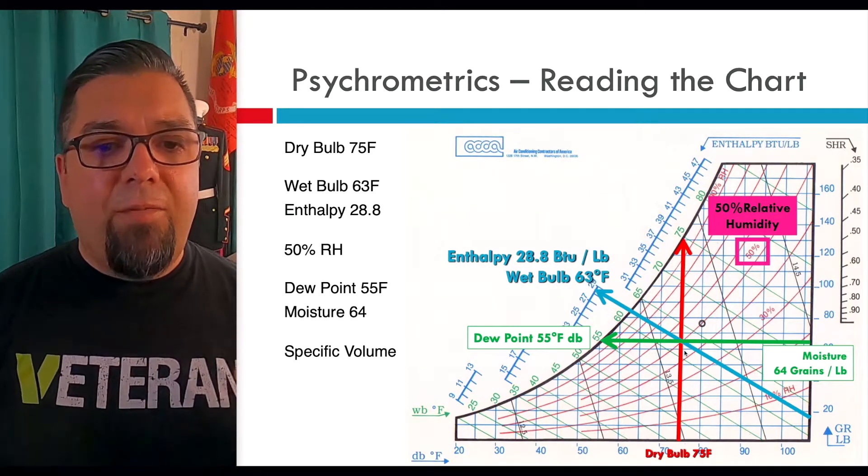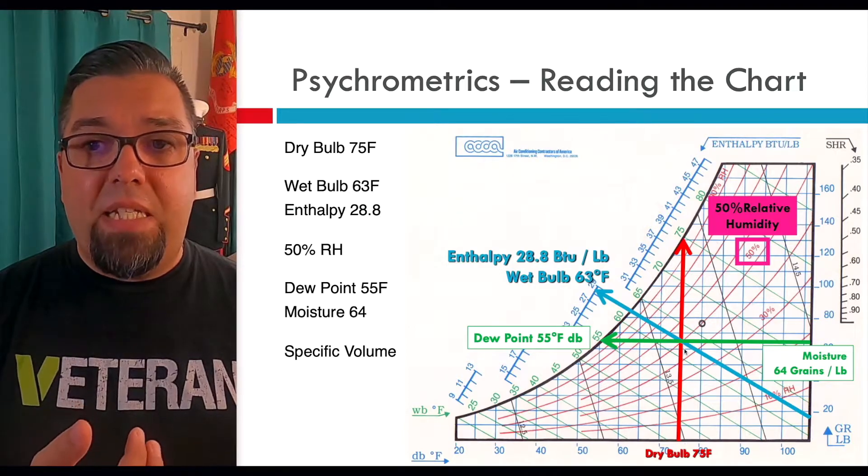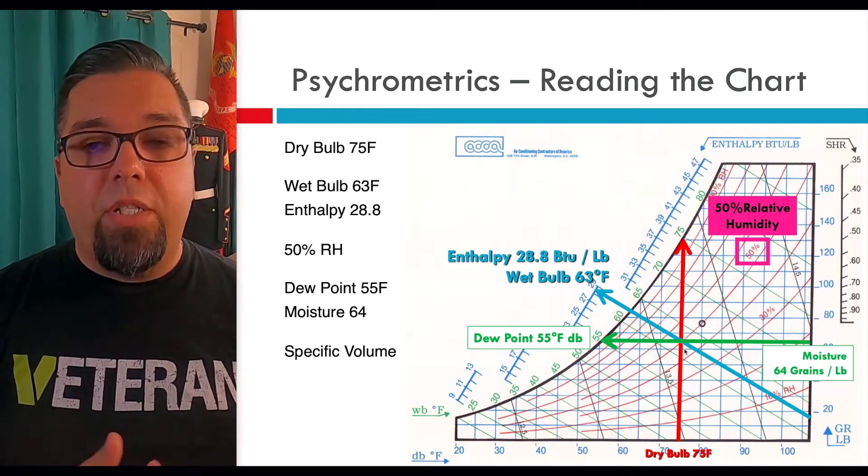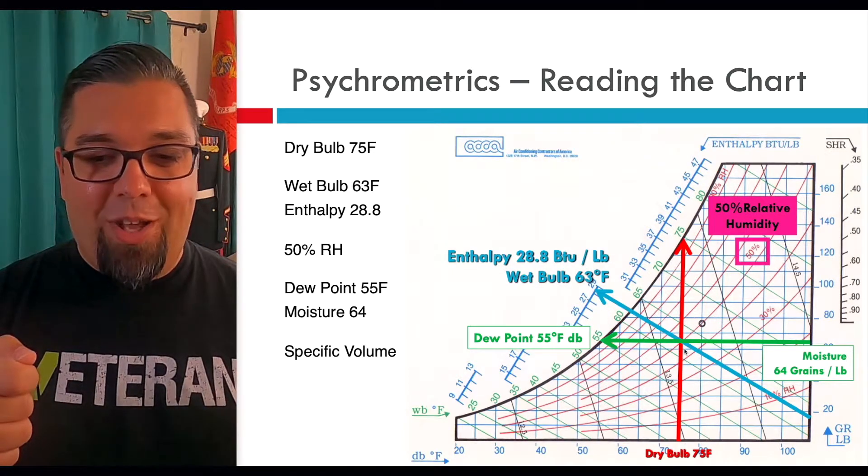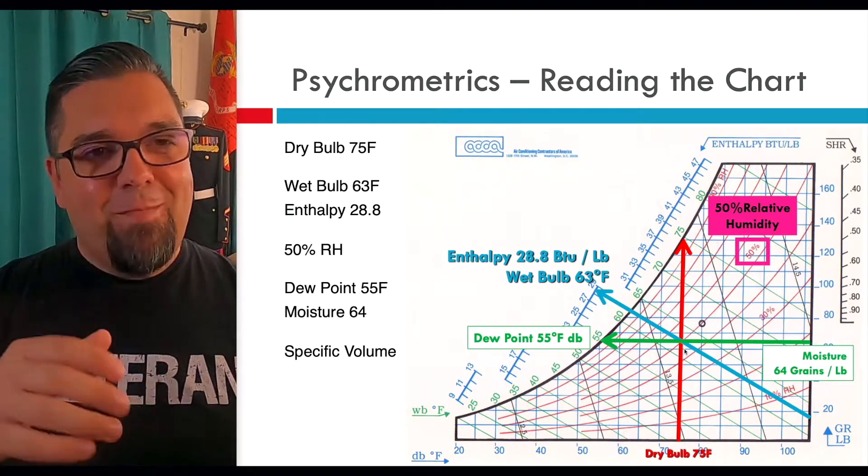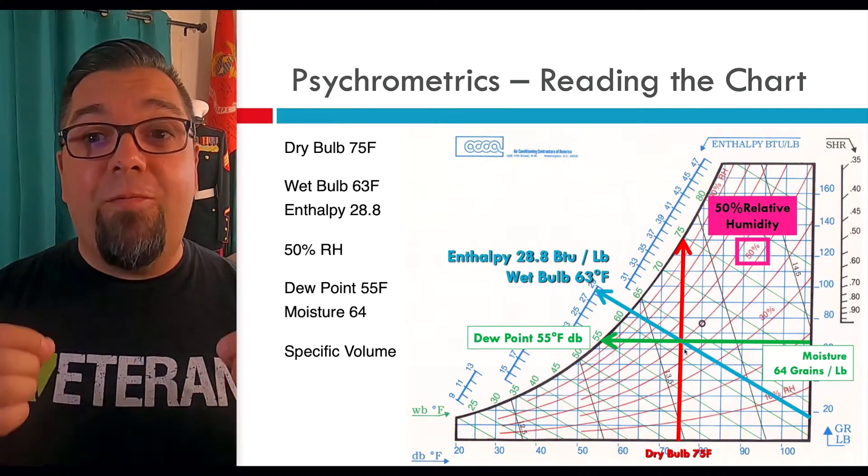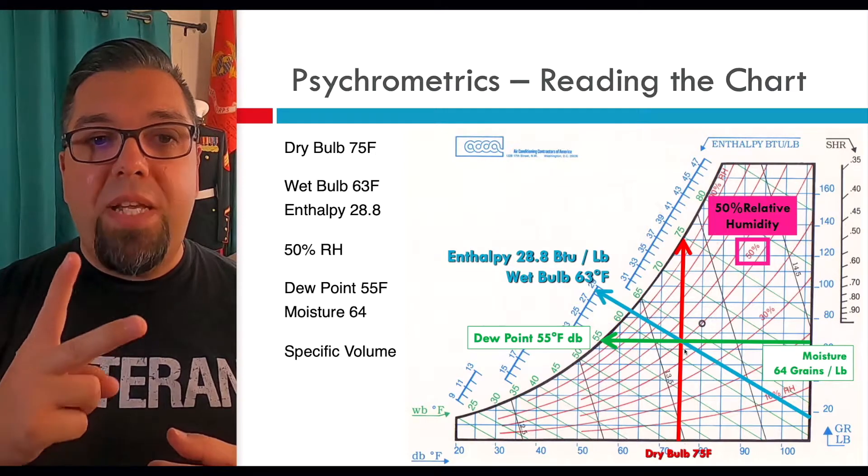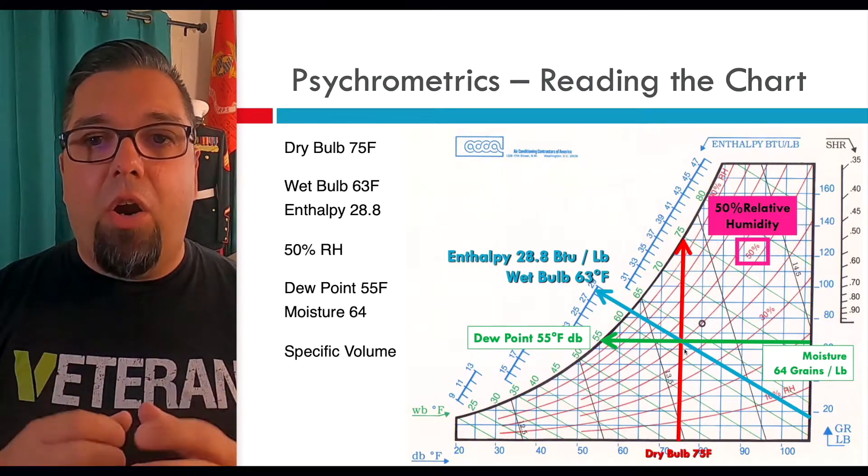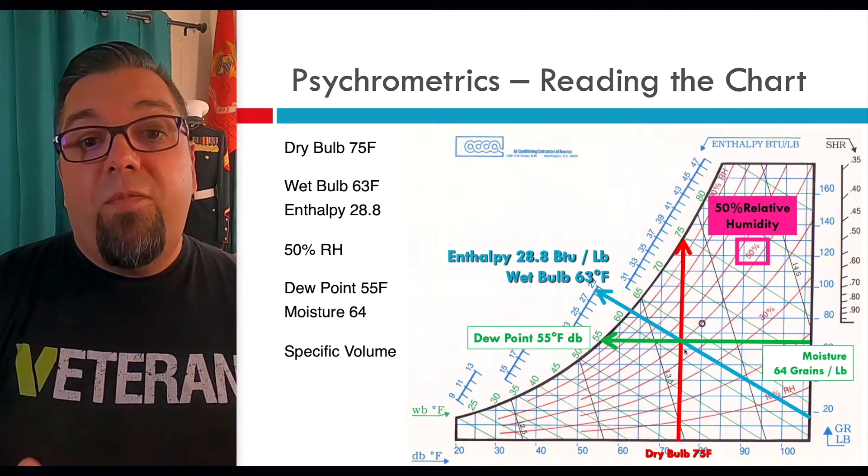Then if I know my wet bulb temperature, and if you guys are in service you probably know dry bulb and wet bulb are probably the two easiest pieces to get off of anything with properties of air. You can measure that very easily these days with digital psychrometers. I personally used to use the old cotton sock, wet it with a type K thermocouple, put it in the return and watch that water evaporate. It was a nightmare. By the time it actually evaporated to get me a wet bulb the dry bulb temperature already changed. So now we have fast accurate tools.